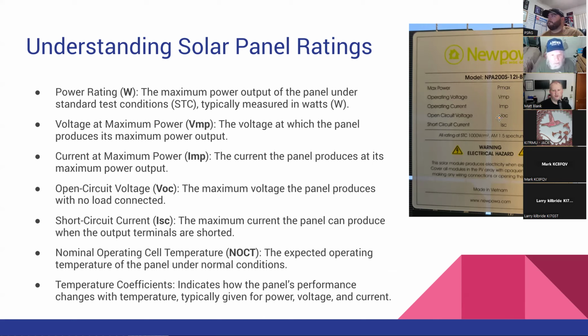These other numbers are for more planning purposes. Open circuit voltage is very important when connecting strings together - this is the number you add up when sizing your charge converter or charge controller. You want to make sure the sum total of the open circuit volts does not exceed your charge controller's input. There's a bit more to this.